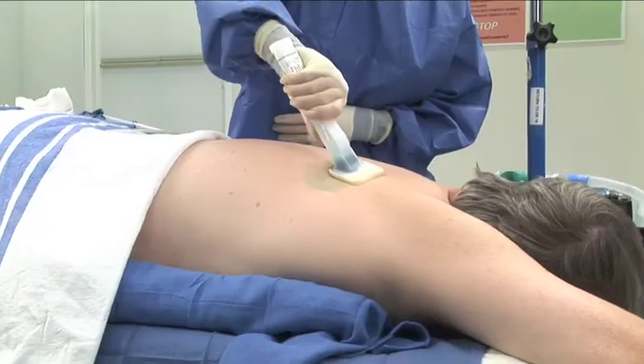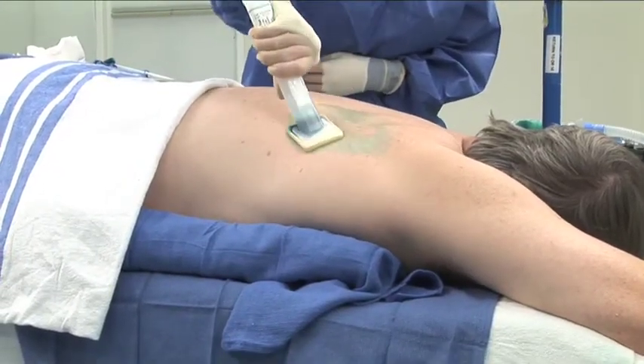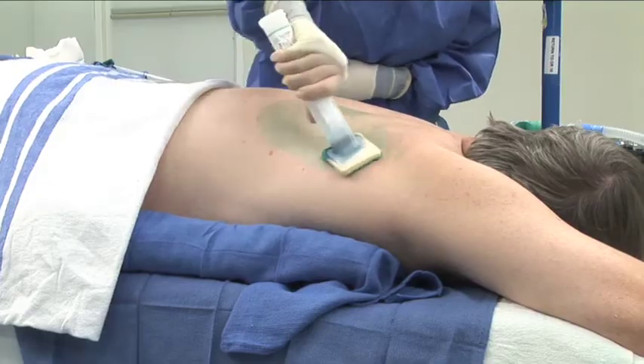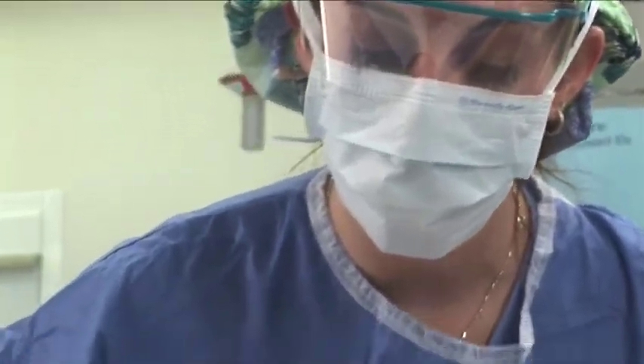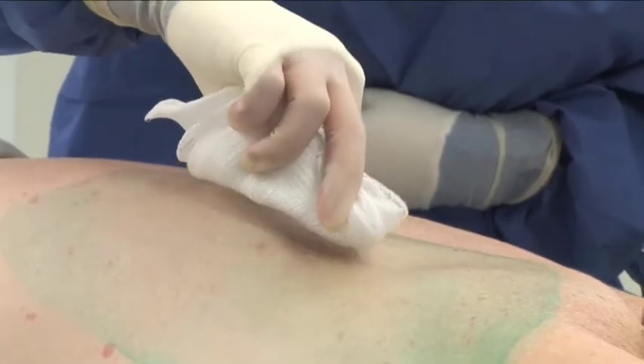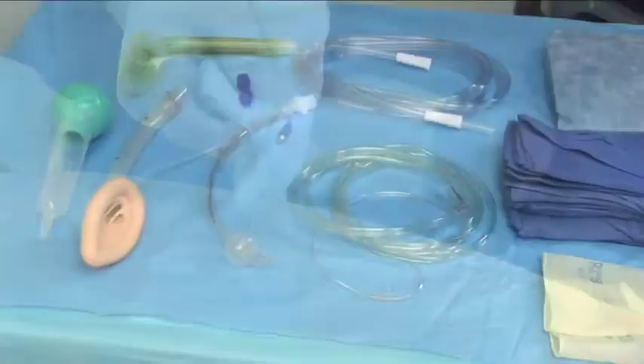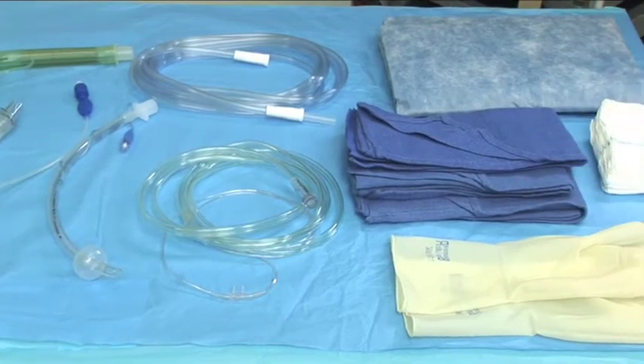Like oxygen-enriched fires, alcohol-related fires can cause serious injury. Alcohol-based prep solutions burn readily in room air, and the fires are hard to see. Fires with any alcohol-based product can cause serious injury. If you use a prep solution containing alcohol, it must be allowed to dry completely before draping. The same holds true for any tinctures or flammable dressing, such as collodion. They must be allowed to dry before use of an electrosurgical pencil or other ignition source near them. Many other surgical items burn vigorously in the presence of enriched oxygen.